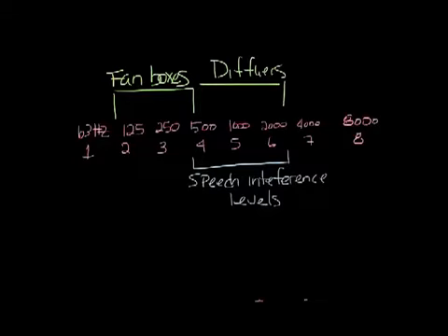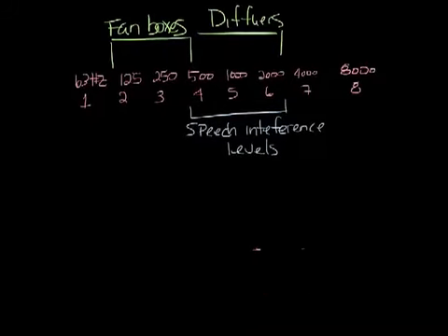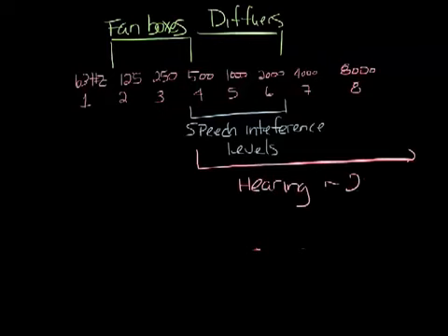You often see HVAC data shown in octave bands 2 through 7 only, because that's where the product's sound level peaks. But in room design, high decibels in the 1st and 8th octave bands can also cause problems. Okay, so let's scoot this out of the way a little bit. As I mentioned earlier, we're more sensitive to certain frequencies. For instance, at high frequencies, about 4th band and higher, the threshold for hearing is 20 dB or lower. At 4,000 hertz, we can actually detect sounds as low as 0 dB.